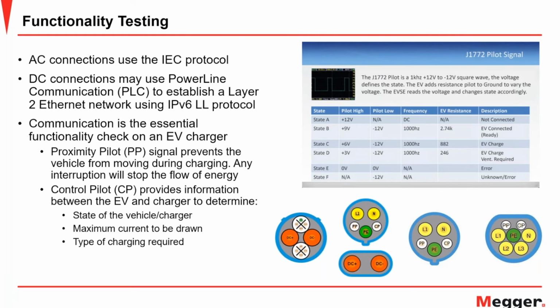A few things to keep in mind that need to be checked as well in the communication protocol. The proximity pilot is a very important safety protocol. The proximity pilot is there to communicate between the electric vehicle and the charge point that the vehicle is there and charging is happening, because any interruption to that proximity pilot signal, for safety, charging needs to be disconnected. That's an important safety communication that has its own channel and is there all the time.